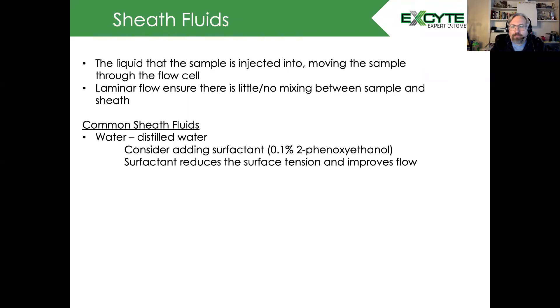For high throughput systems, having just pure water with surfactant is better because you don't see a lot of crystallization, which can happen especially if the HTS is not used regularly. Of course, this is not for sorting.